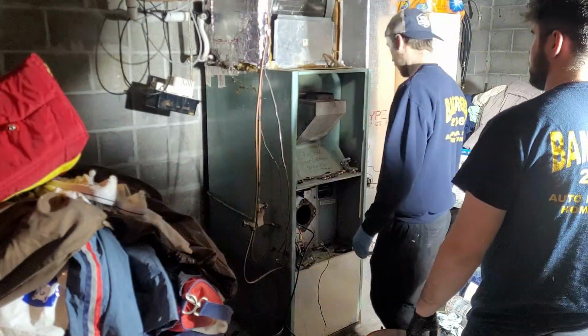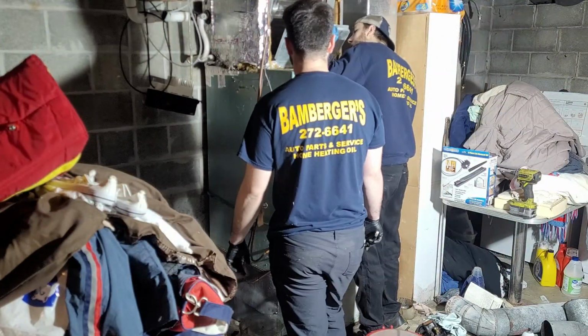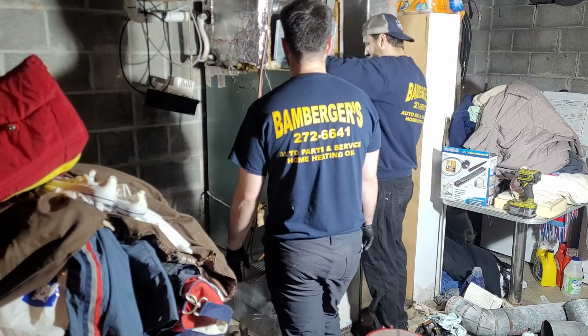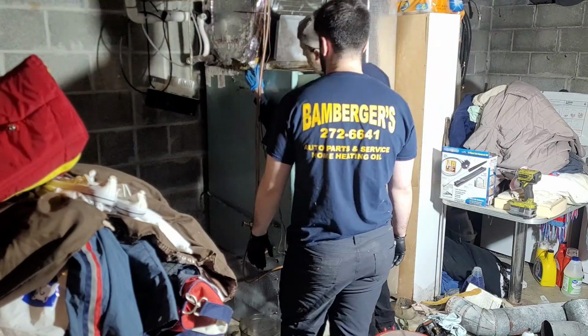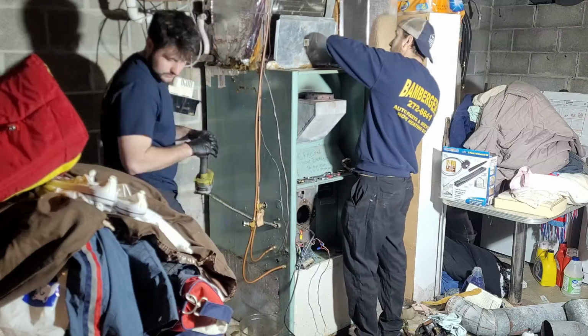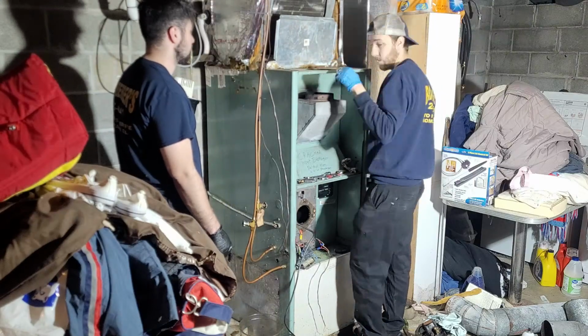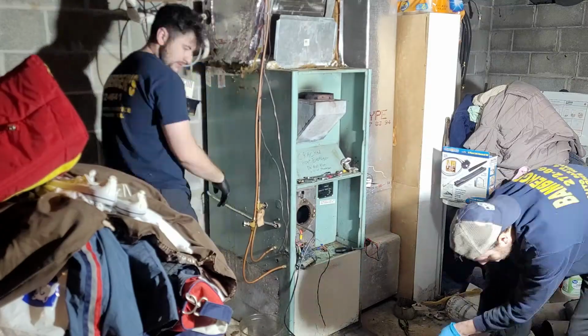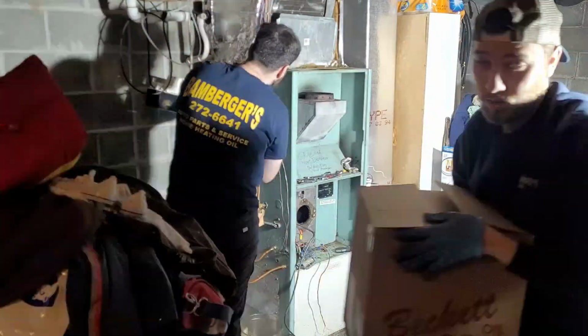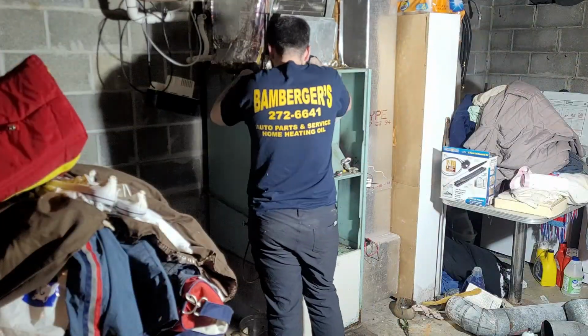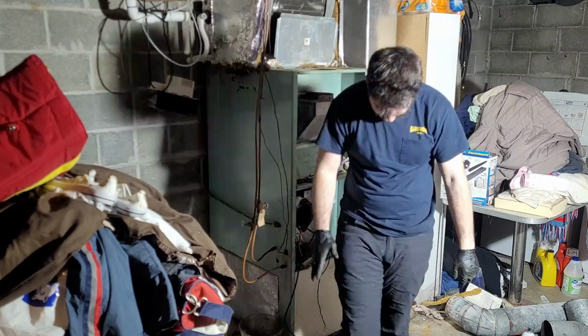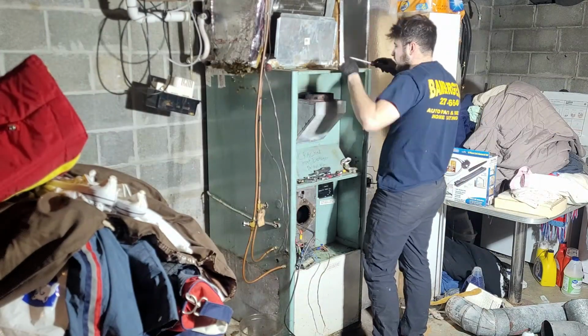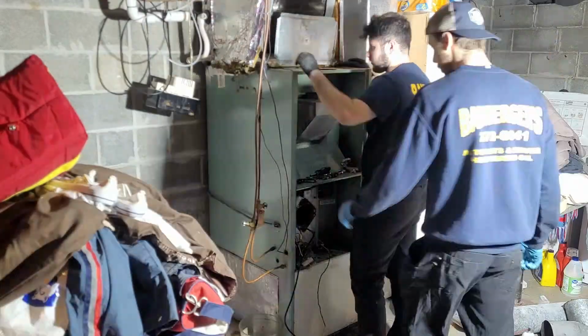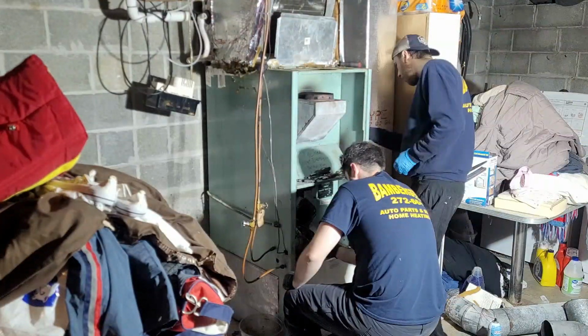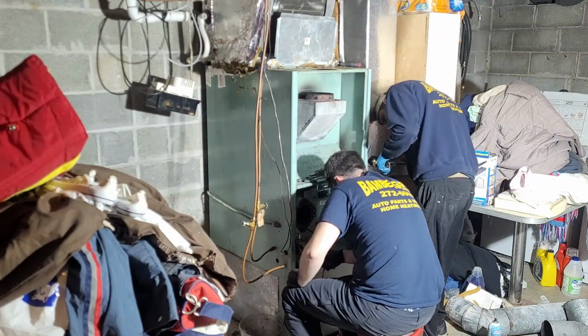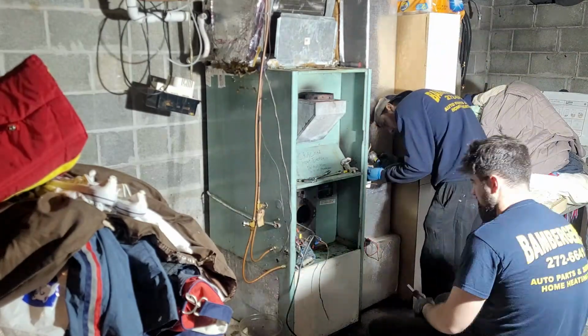Riley was cutting off the front of the ductwork, which was necessary because we needed to support the upper ductwork where the coil for the air conditioner sits. We had to lift that up and support it with cables — I think we used ratchet straps — so we could pull the old furnace out and get the new one in. This was pretty difficult because the original installers built it without swapping in mind.